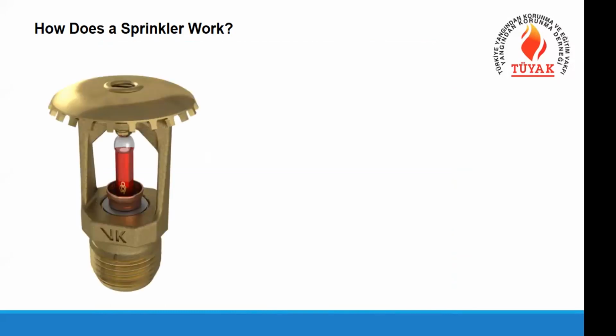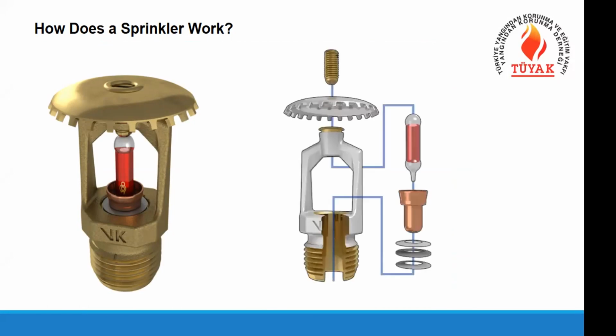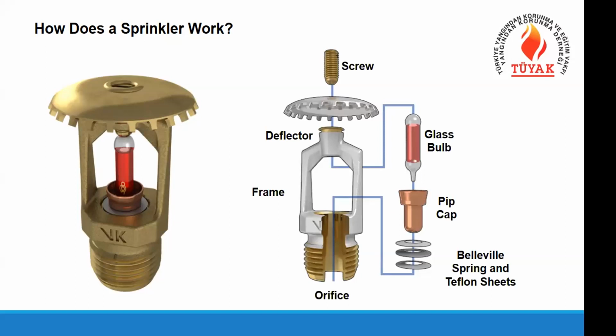So when we look at a fire sprinkler, it looks like a single part, but it's composed of many items. It has different parts to make it a complete actuating device. It has a water hole, called the orifice, and it's defined by the water flow per the pressure behind the sprinkler, and you have a defined value of K factor, increasing with the fire hazard or the installation height. So you have different kinds of sprinklers with different K factors, namely different flow rates of water when you need to open the sprinkler during a fire.